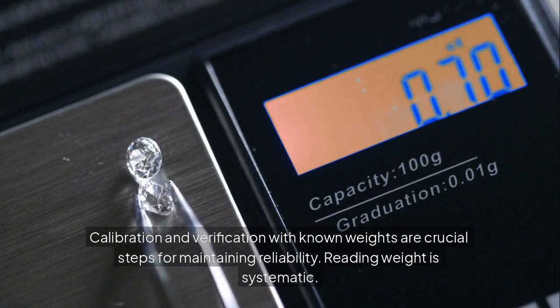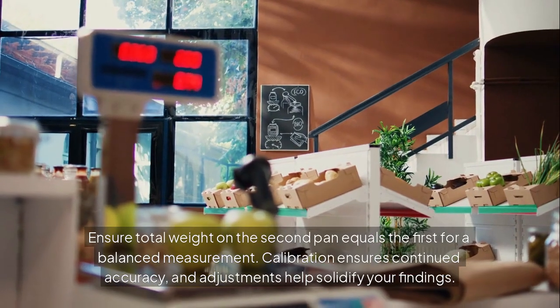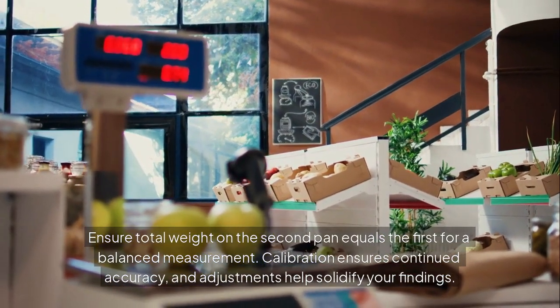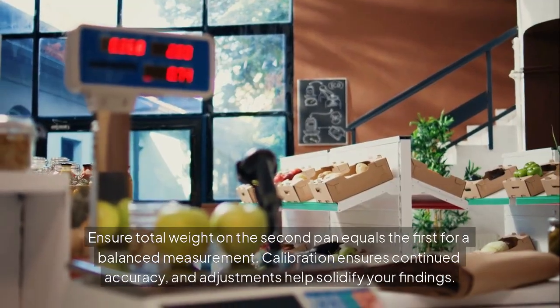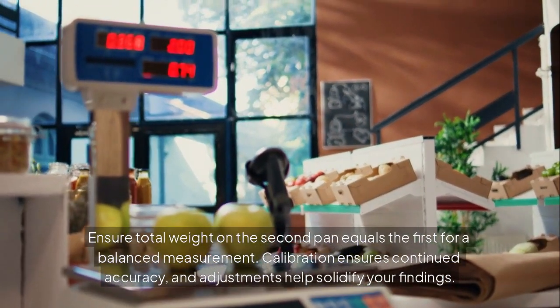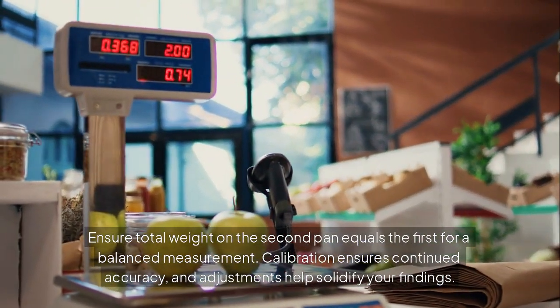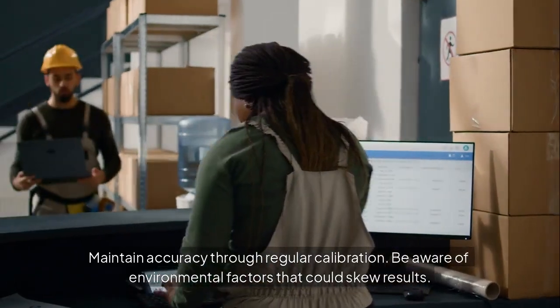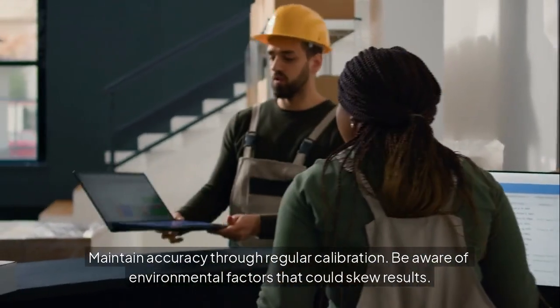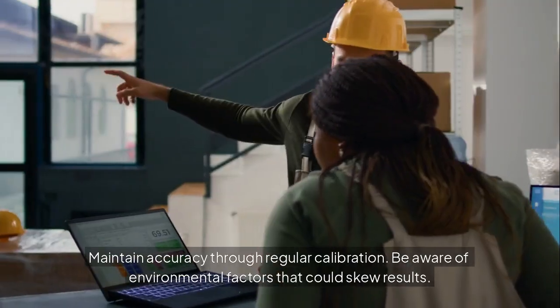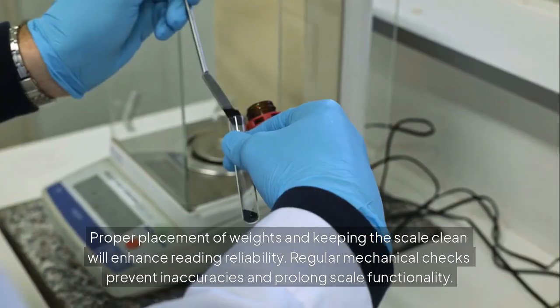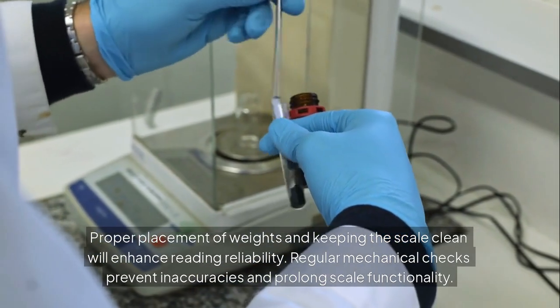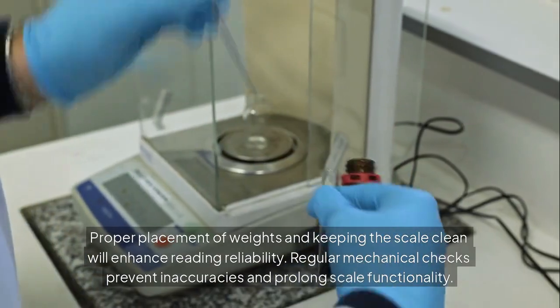Reading weight is systematic. Ensure total weight on the second pan equals the first for a balanced measurement. Calibration ensures continued accuracy, and adjustments help solidify your findings. Maintain accuracy through regular calibration. Be aware of environmental factors that could skew results. Proper placement of weights and keeping the scale clean will enhance reading reliability.